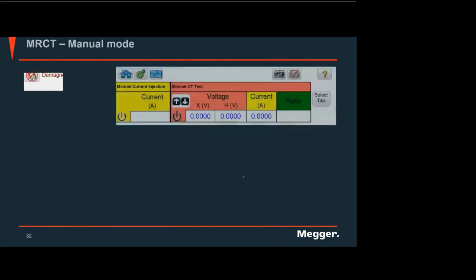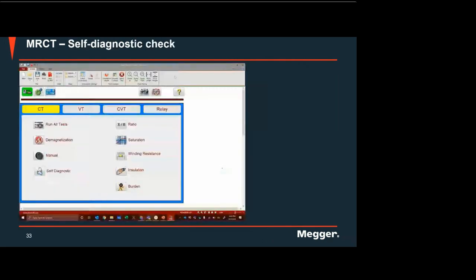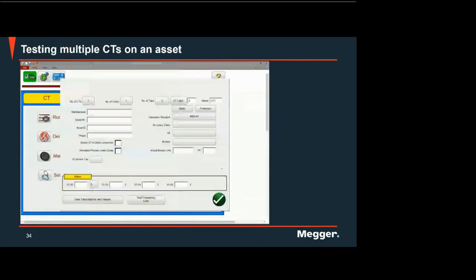And then you have also the manual control, this knob here. So if you want to experiment, if you want to do something, then you have the right to control the current or the voltage. You can control the current, you can control the voltage, so you can have the ratio. So this equipment also has a self-diagnosis check. Meaning you can check if the equipment is still working or in good condition. But it's not a calibration check. It's just a simple self-diagnostic check, right?